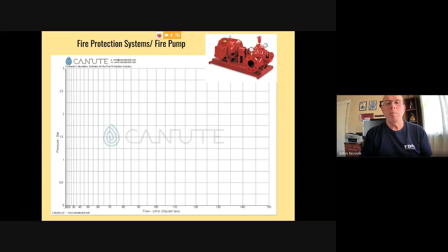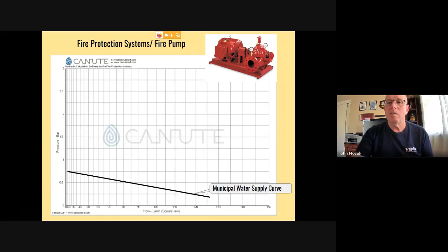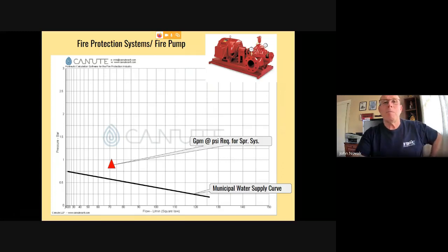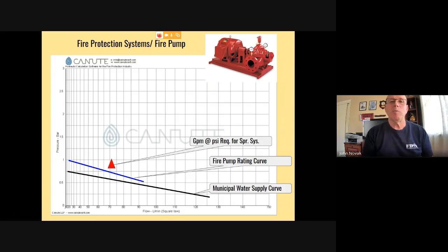And the reason we put the pump there is because when we build a building and it needs a sprinkler system, we look at the municipal water supply curve. So here the black line represents the water supply from the city, and the red triangle is the required water flow for the sprinkler system. So in this case, the municipal water supply does not meet the pressure that's required for that sprinkler system in that building. It could be a multiple floor building, you could have an area of bad water, a lot of factors go into that. So in order to get the required amount of pressure and flow, the building owner is going to have to put in a fire pump.